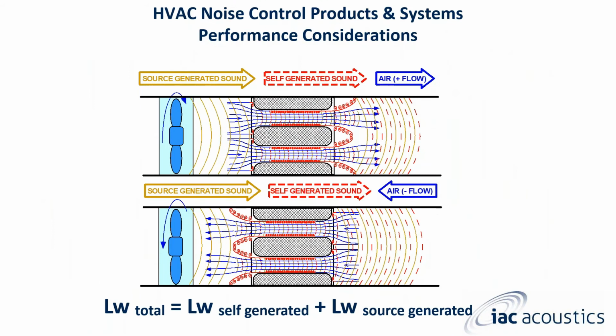Here's another example of source-generated sound. So again, the fan is pushing air through, you might see some self-generated noise through the perf and as it exits, but it's going to quell that as it follows the airflow. Case in point, in reverse, it's going to be pulling it to the fan. So again, the noise is after the silencer, not right there at the fan, not before.